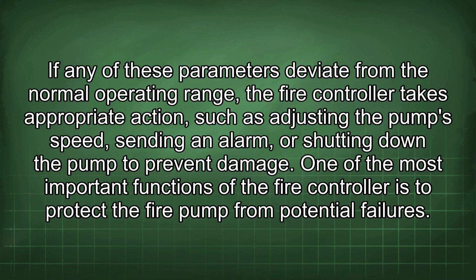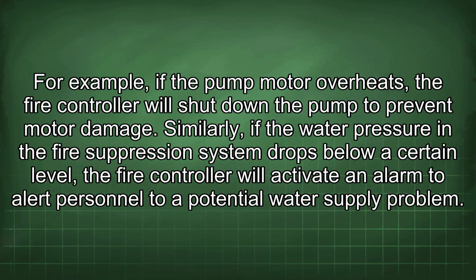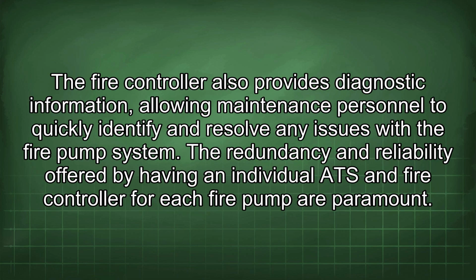One of the most important functions of the fire controller is to protect the fire pump from potential failures. For example, if the pump motor overheats, the fire controller will shut down the pump to prevent motor damage. Similarly, if the water pressure in the fire suppression system drops below a certain level, the fire controller will activate an alarm to alert personnel to a potential water supply problem. The fire controller also provides diagnostic information, allowing maintenance personnel to quickly identify and resolve any issues with the fire pump system.